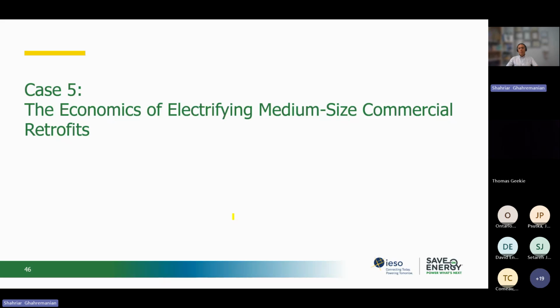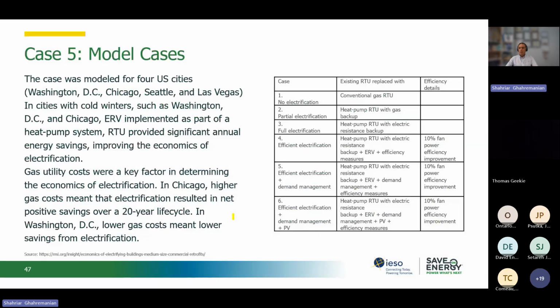Now, I want to show you a case of the economics of electrifying medium-sized commercial retrofits. This study was done for different cities in the US, but I just picked Chicago because its climate might be closer to ours in Southern Ontario, for example. They said that in the conventional or baseline system, we have conventional gas rooftop units. For the second option, they retrofit with a heat pump rooftop unit with a gas backup, or option three is the heat pump rooftop unit with electric backup.